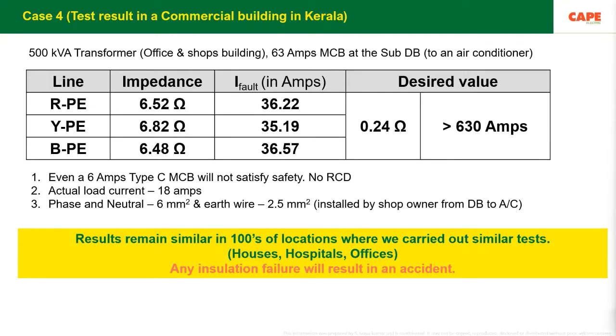And then we got in touch with the designer of that particular building. Interestingly, he said that no, this cannot happen in my building because I designed the building based on IS 3043. And when we asked, did you hear of fault loop impedance? He said yes, I did as per IS 3043, but he never heard the name fault loop impedance. And this name is written in IS 3043 in 66 places. This name, its definitions, its application are written. In IS 732, about 62 places, fault loop impedance and disconnection times and disconnection methods are explained. But this is unknown to the user. Of course, he is not an electrical engineer, but it is unknown to the contractor, unknown to the designer. This is the pathetic situation.